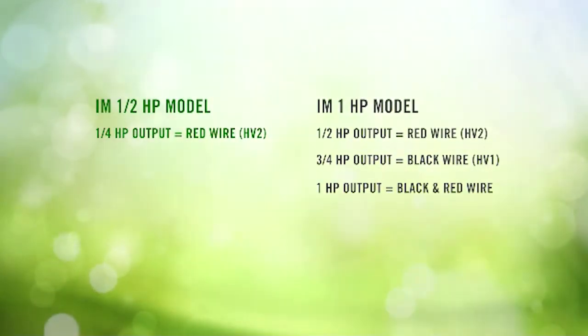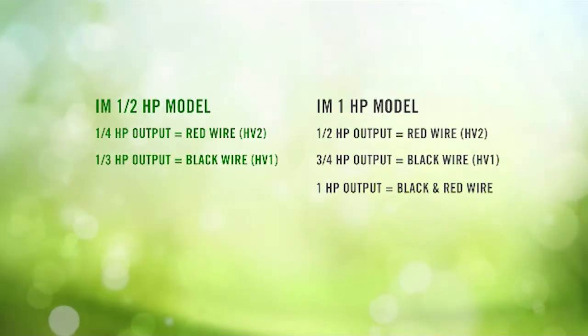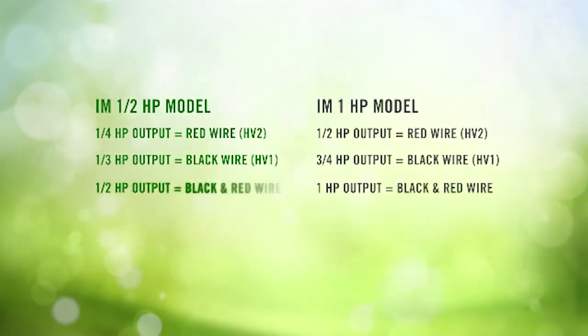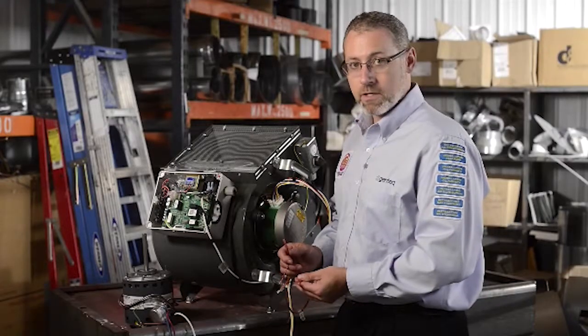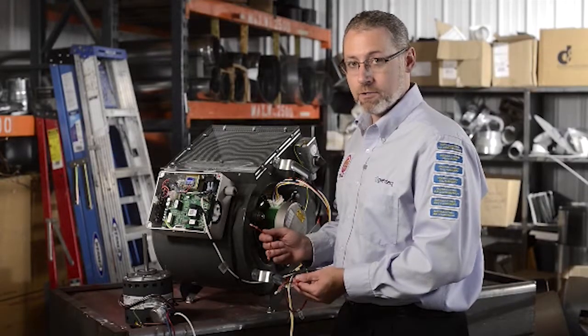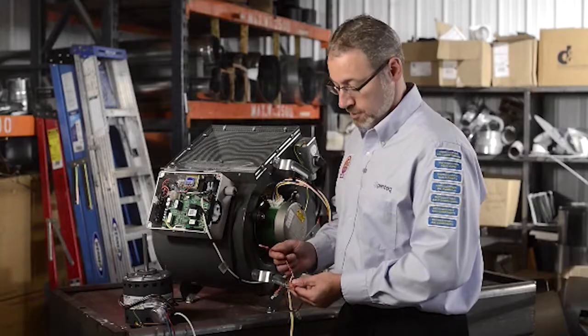the red wire only. If I want the 1/2 horsepower motor to run at 1/3 horsepower, I would use the black wire only. And if I want that 1/2 horsepower motor to run at a full 1/2 horsepower, I would connect both the red and the black wires to those speed taps. So let's say we're going to use this 1/2 horsepower motor as a 1/2 horsepower motor.